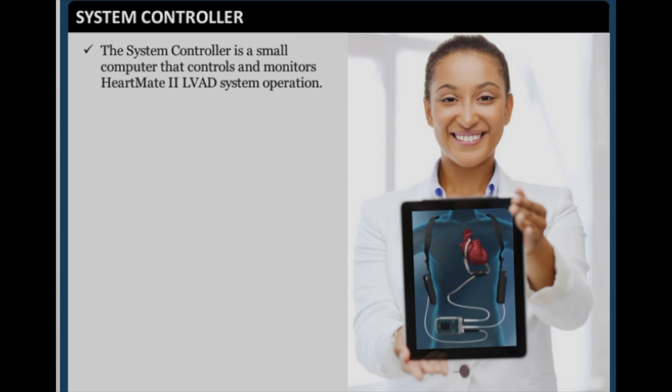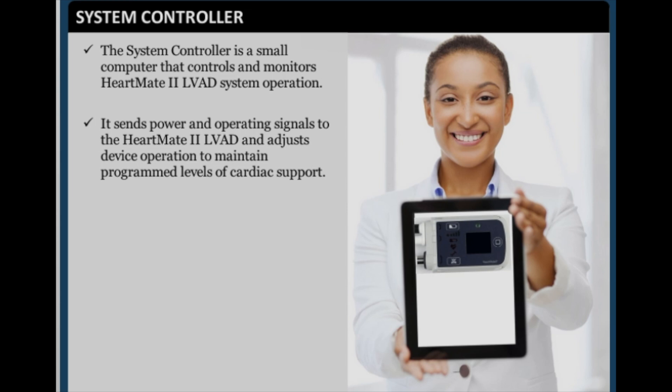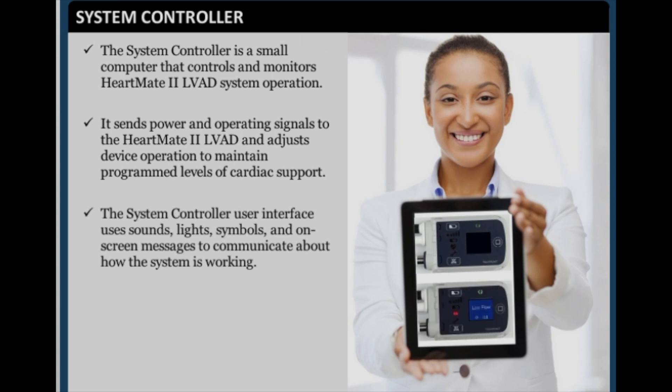The system controller is a small computer that controls and monitors HeartMate II left ventricular assist device system operation. It sends power and operating signals to the HeartMate II LVAD and adjusts device operation to maintain programmed levels of cardiac support. The user interface on the system controller is the primary interface for users during routine system operation. It uses sounds, lights, symbols, and on-screen messages to communicate about how the system is working.